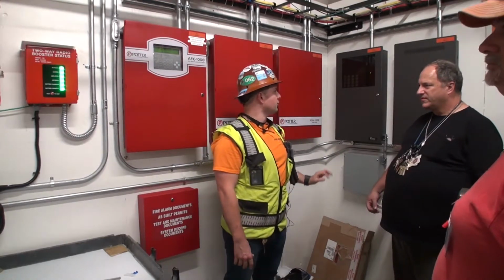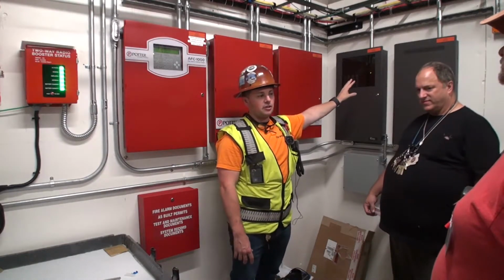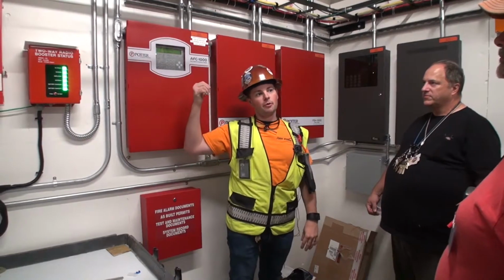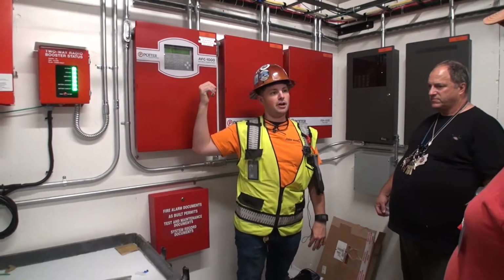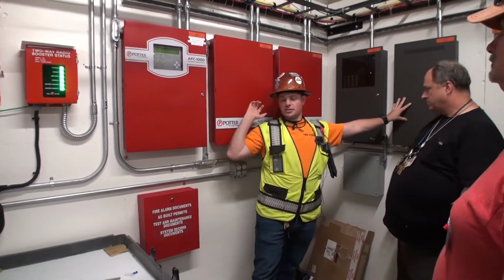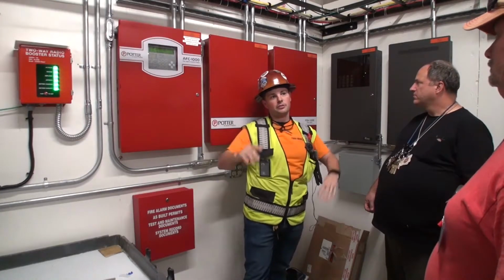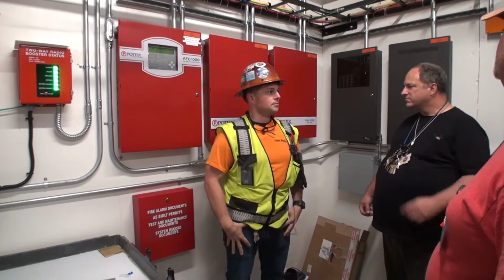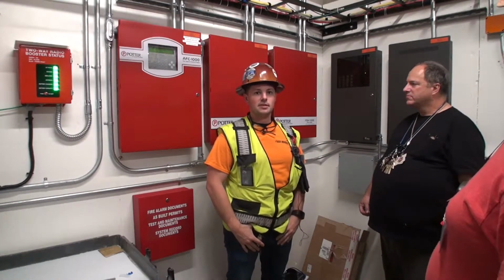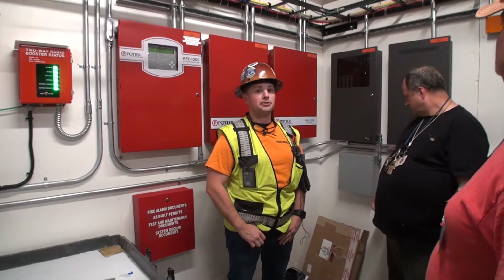Any trouble on the voice evac system will tell you what the specific trouble is down here on the amplifier panel, and will come up with a generic voice system trouble on your fire panel. This is an auxiliary amplifier, and these are just strobe panels. That's all that's located in the other electrical rooms, is more of those. And every panel again has batteries in it, and will report into the panel with which panels have battery trouble.